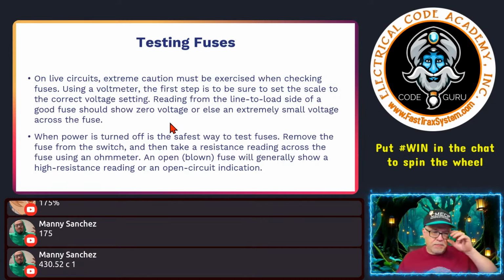All right, so testing fuses. On live circuits, extreme caution must be exercised when checking fuses. Using a voltmeter, the first step is to be sure to set the scale to the correct voltage. That should be a no-brainer for all you electricians if you're working with AC. Put it in AC, all right? Very, very little time are you going to be in DC unless you're troubleshooting something on a board, that type of thing, operating through a rectifier that's actually giving you DC. Not going to be what most of you and I do. We want to make sure that we're on the right setting.